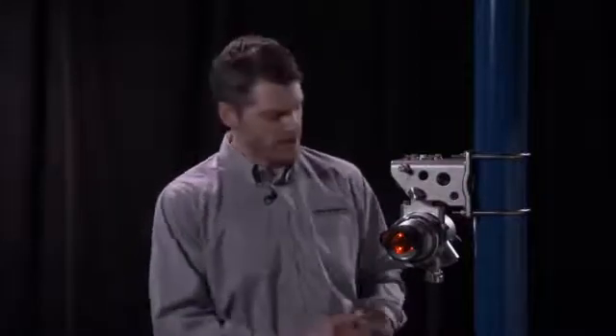60 seconds have passed and we can see that our receiver is now indicating a fault condition as expected. I know that because I have a yellow LED and if I were to count the number of flashes of that yellow LED I could look at my instruction manual and see exactly what fault that indicates. In this case I'm getting seven flashes. That indicates that I'm in a beam block fault which is exactly what we would expect because I've taken this receiver and I've misaligned it to the point where it's no longer receiving any light from the transmitter.